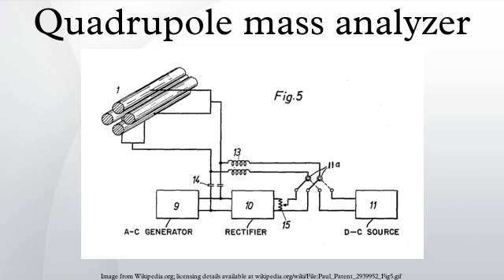Principle of Operation: The quadrupole consists of four parallel metal rods. Each opposing rod pair is connected together electrically, and a radio frequency voltage is applied between one pair of rods and the other. A direct current voltage is then superimposed on the RF voltage.